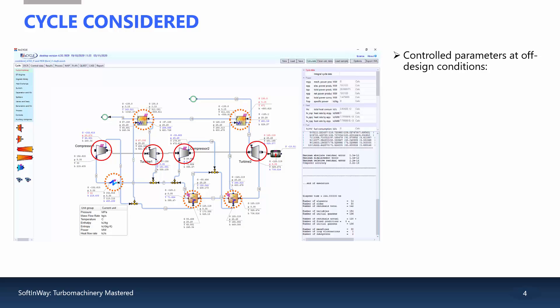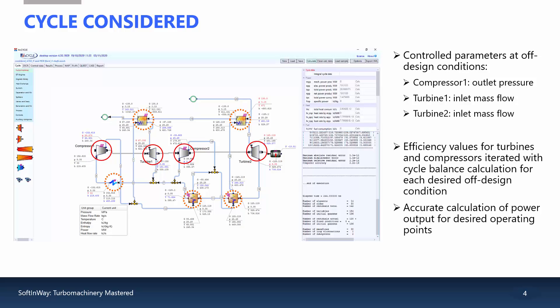For each desired part load mode, we need to provide some initial values to obtain the desired output power. These initial values include compressor 1 exit pressure, turbine 1 mass flow rate, and turbine 2 mass flow rate.